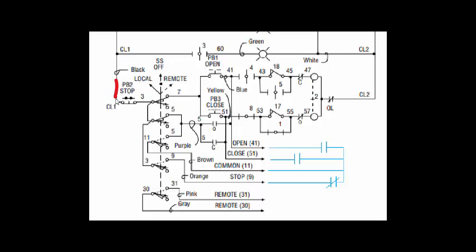and voltage will go through the normally closed stop button as long as we're not pressing it and come over to the selector switch. The selector switch has three positions: off where none of the contacts are made up, local where we see a solid line. If we're in local we will follow the path of that solid line.